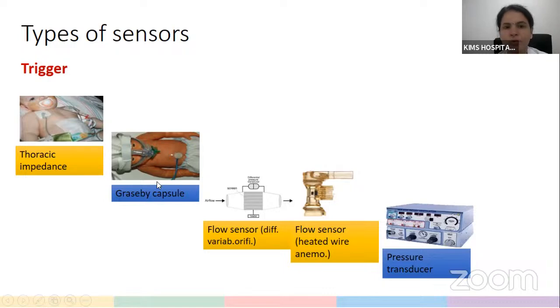Now, both these types of sensors are quite imprecise. They are quite insensitive also, because they require a significant patient effort for us to sense that the baby has initiated a breath, and hence the work of breathing of the baby can become more. Also, they can come with the problem of artifactual triggering due to non-respiratory movements of the baby, such as hiccups.